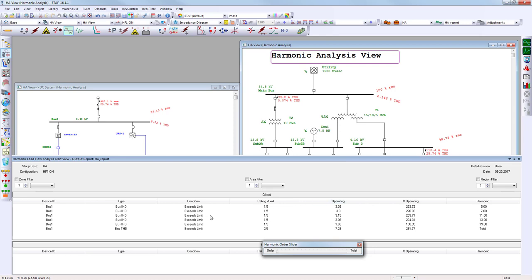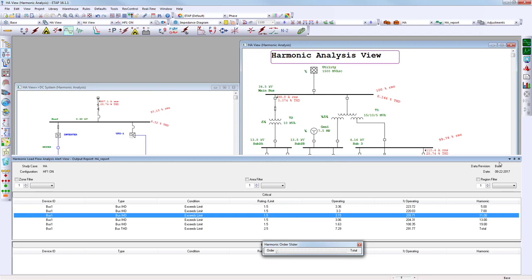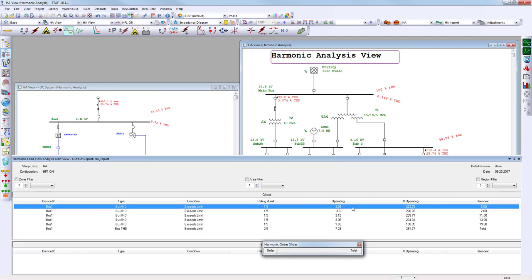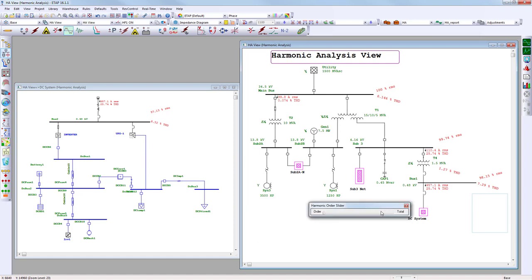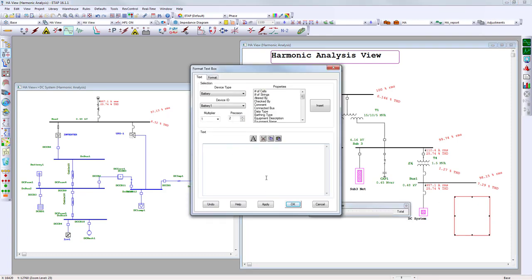Looking at the alert view, we do have issues at bus number one. We have a limit of 1.5% but we're operating well above that. The total harmonic distortion at bus number one is 7.29%, so that's something we need to correct.